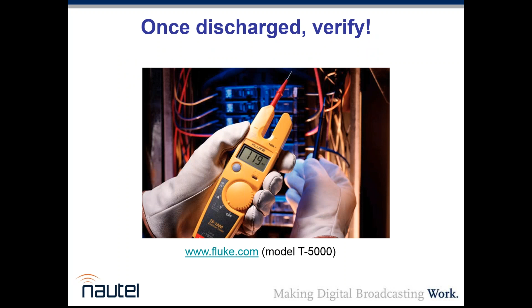Okay. So they're very high impedance inputs, so therefore there's no actual connection to the high voltage. Right. And I mean, the theory is that, and we use them exclusively in the test room and engineering labs. And I showed an example here from Fluke along with the model number for both this and the proximity alert meter. Now, the proximity alert, the volt alert, will only work on AC. It will work to a lesser extent on RF, but I'd want to test it on a known hot circuit before I verified that it did function for that. I sure wouldn't trust it unless I'd actually verified.